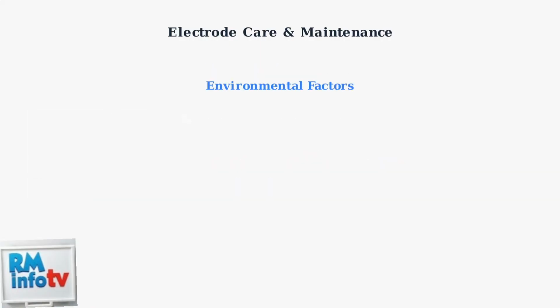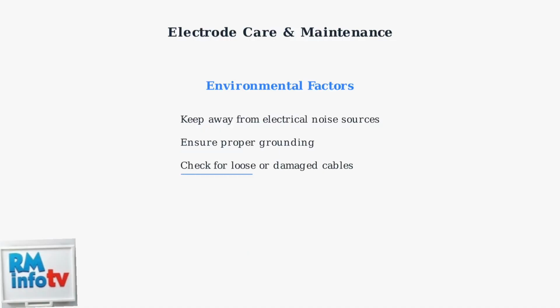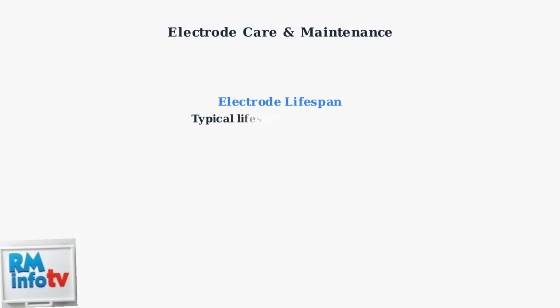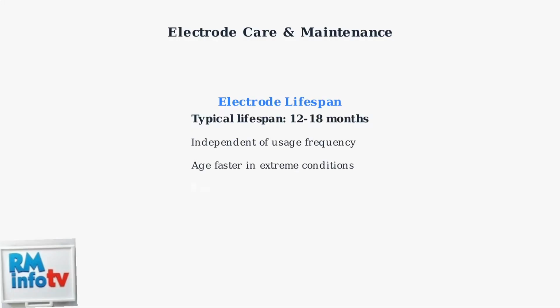Environmental factors can also affect pH meter accuracy. Keep the meter away from electronic devices that generate electrical noise. Ensure proper grounding and check for loose or damaged cables that could interfere with readings. Remember that electrodes typically last 12 to 18 months, regardless of use frequency. They age faster in extreme conditions. Regular maintenance and proper care will help maximize their lifespan and ensure accurate pH measurements.